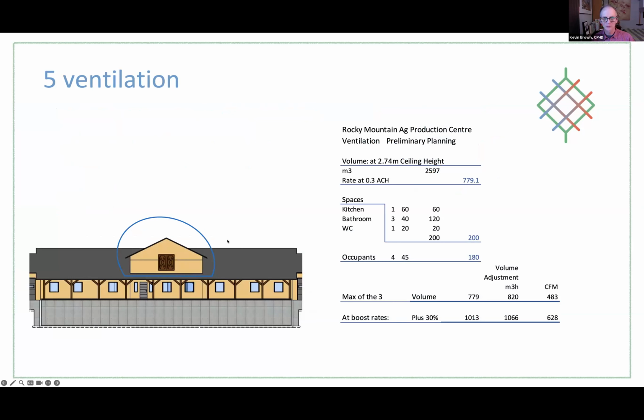With the ventilation system, it was planned to meet Passive House standards, so you do your 3-part test, and indeed the volume of the building, with a volume adjustment in the circled part of the building, because of that high volume space there, we wanted that fully ventilated, mainly to keep heat gain under control if people are working in there in the summertime. That's how we came up with our cubic meters per hour CFM rating for the system, and how we ended up sizing the Swegon RX7.